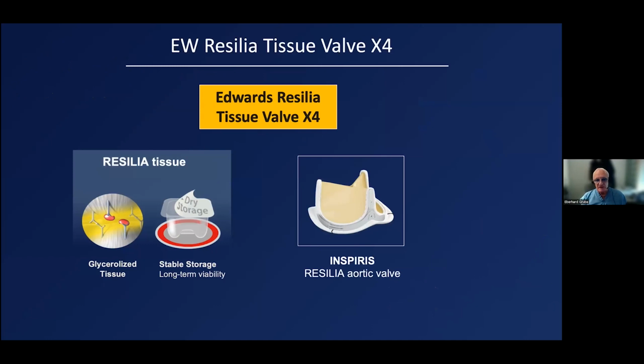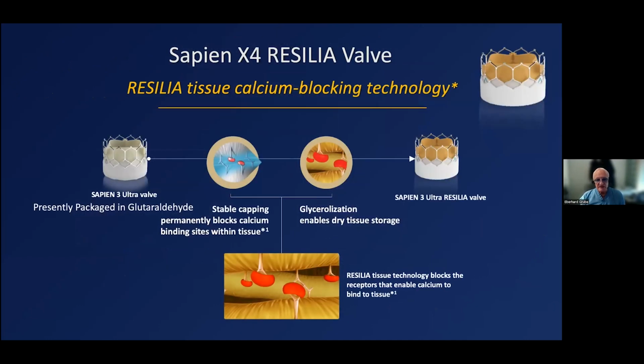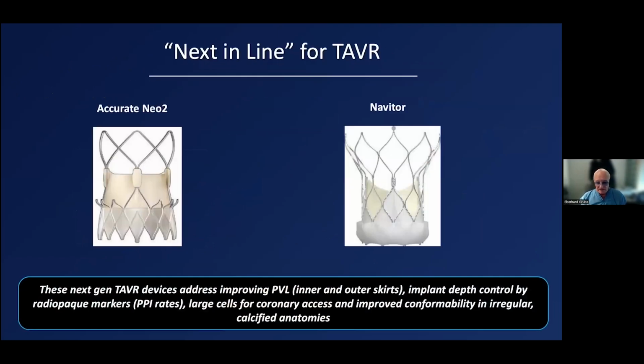The Edwards Resilia tissue valve, dealing with the Resilia tissue calcium blocking technology, dealing with the leaflets' anti-calcification treatment to ensure longer durability. This valve is being used both in surgery and in TAVR valves.